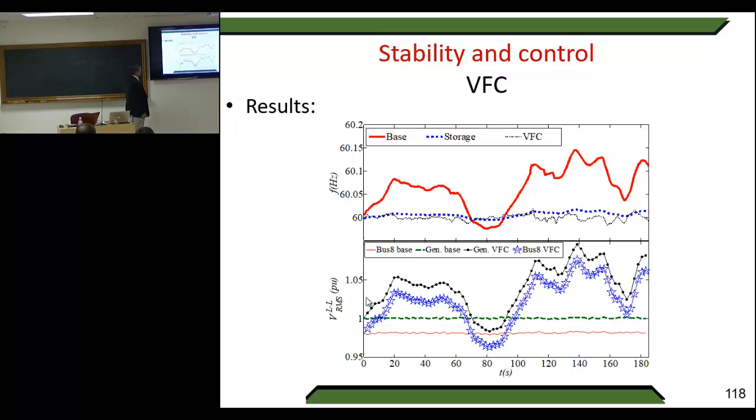And with the same picture as before, you can see that the results here with the generators, with the voltage frequency control of the genset, can reduce, in this line compared with the other one, only with the management of the load voltage dependency. So you can move here in a nice way with this capability, and you can exploit this. Again, try to avoid storage or increasing the cost in the system, and only if all the strategies are not enough, then you go to new investment.